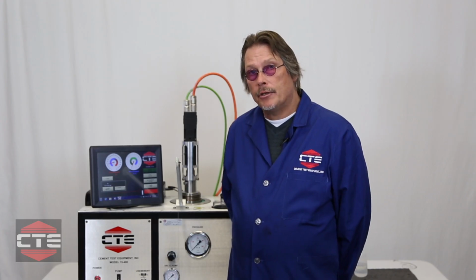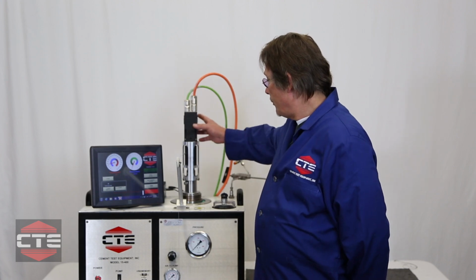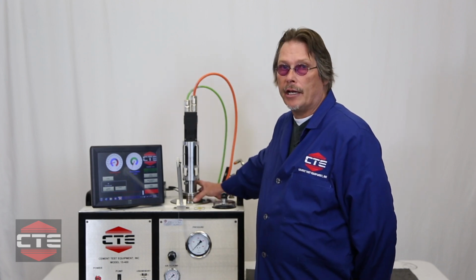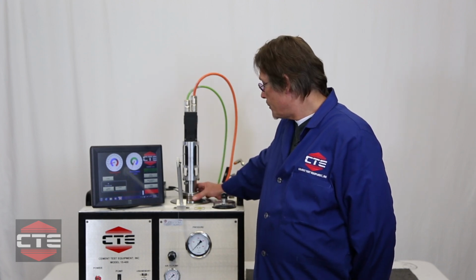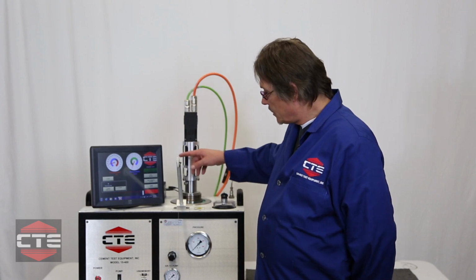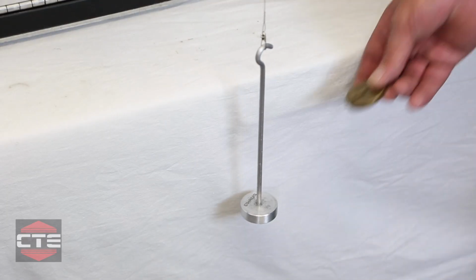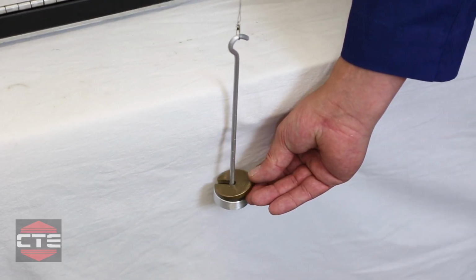We're now set up to do calibration of consistency. As you can see, I have the motor attached to an empty cell, paddle only in the pressure vessel, head engaged, cable on the calibration arm, and we're going to start with 100 grams of weight.